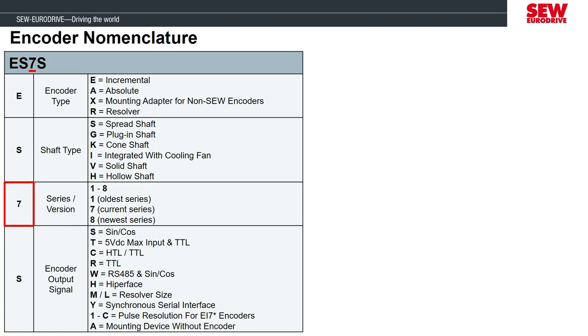The series number is important because it represents mechanical differences in the shaft design. For example, if you have an old DT motor and need to replace the encoder, you wouldn't be able to install a seven series encoder on the old motor. You would need to replace the encoder with the same series if it's still available, or replace the whole motor to use the new series. The last letter indicates the type of signal the encoder outputs, and some output signals are only possible with resolver or absolute encoders.